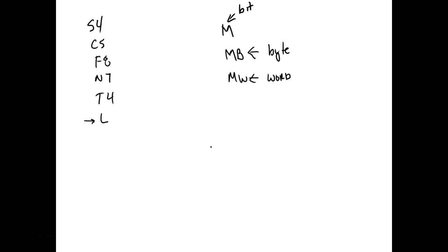So this is one big difference with Allen Bradley's RSLogix 500 and Siemens: the minimum data file that we can have is 16 bits. B3, that's a dedicated word. Siemens has no dedicated files, it's memory, and we decide what goes where, right? You understand that? We don't have a bit dedicated to this. We specify the length that we're dealing with by the way we address the memory.